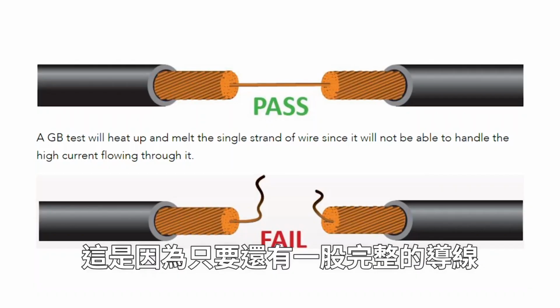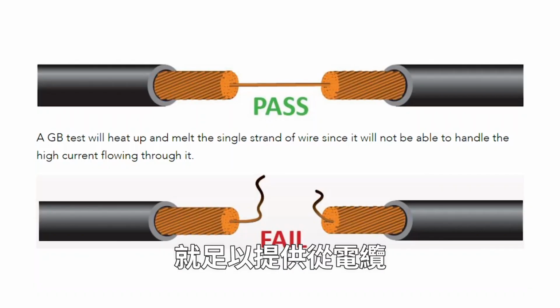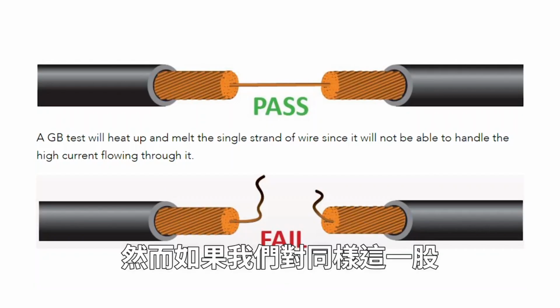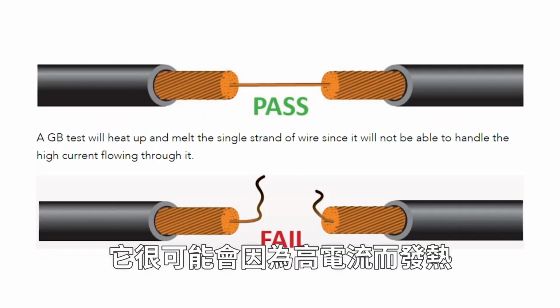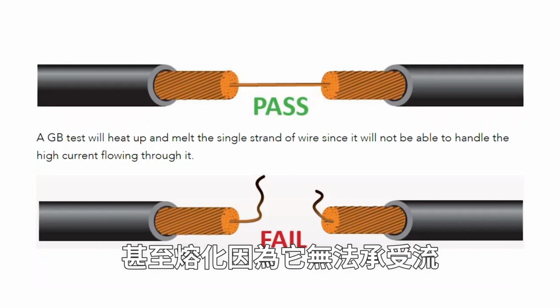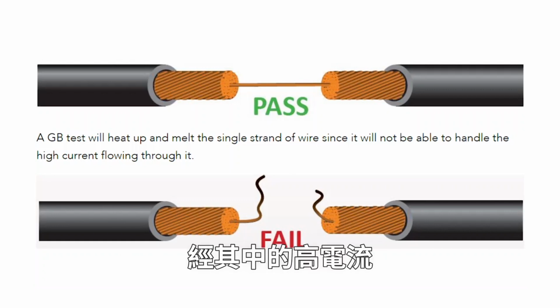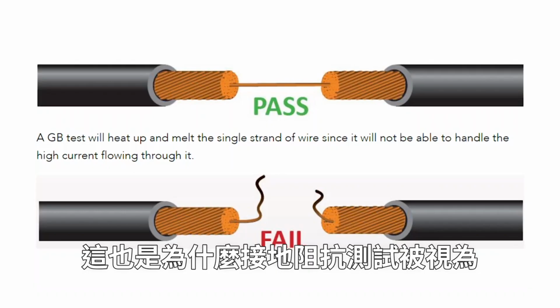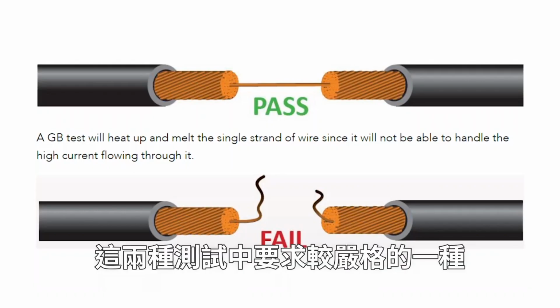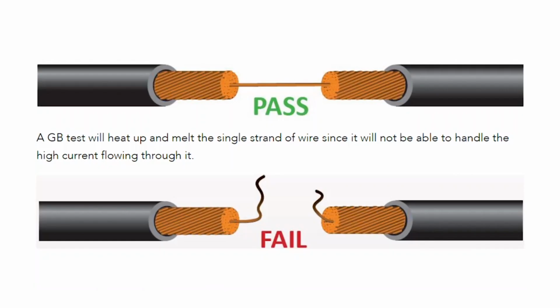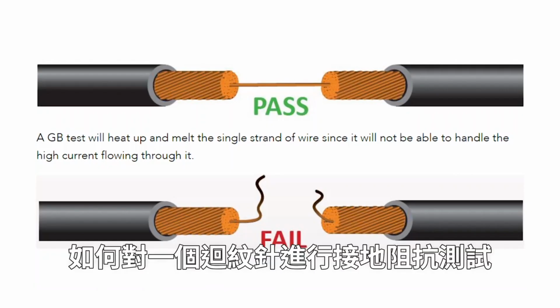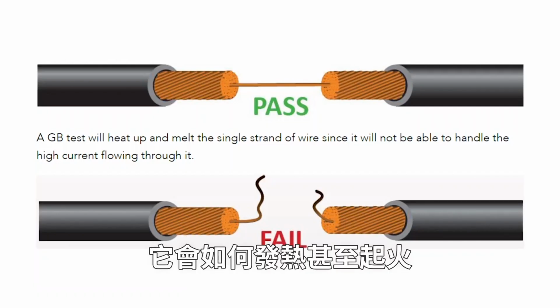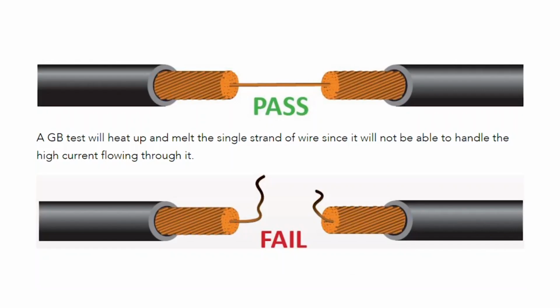This is because the single strand of wire that's intact will be enough to provide continuity from one side to the other. Whereas if we were to perform a ground bond test on the same single strand of wire, it will most likely heat up and melt, since it will not be able to handle the high current flowing through it. And this is why the ground bond test is regarded as the more stringent of the two tests. Next, we will take a look at a ground bond test being performed on a paper clip, and you can see for yourself how it's going to heat up and catch fire.